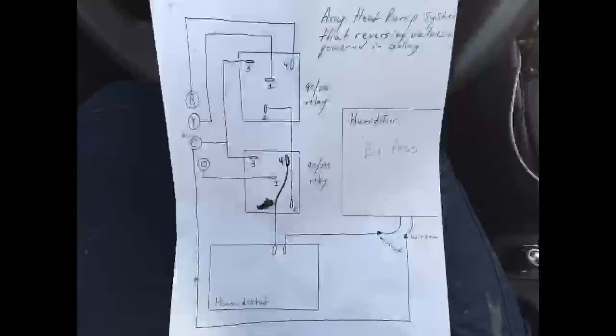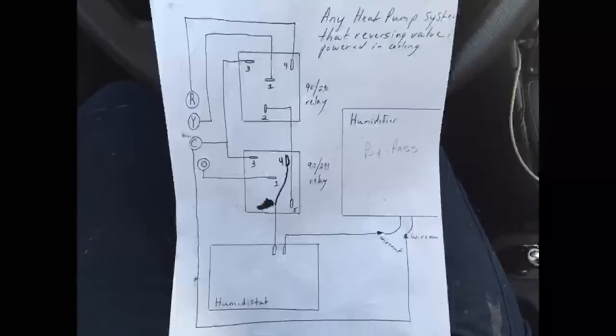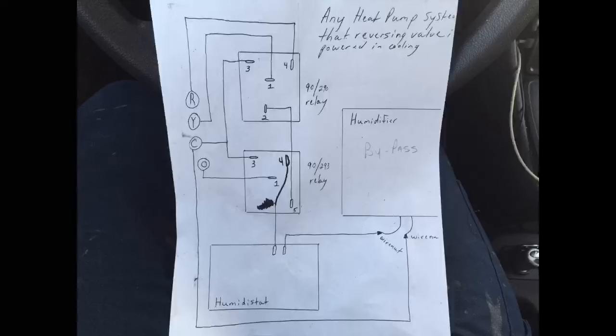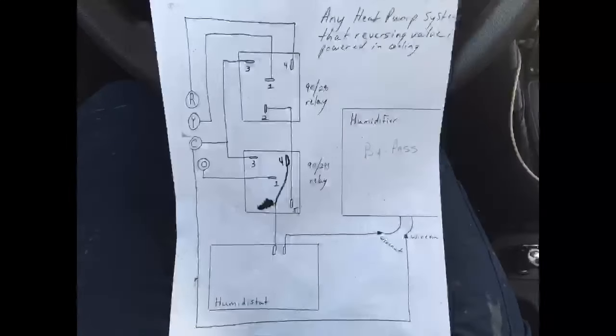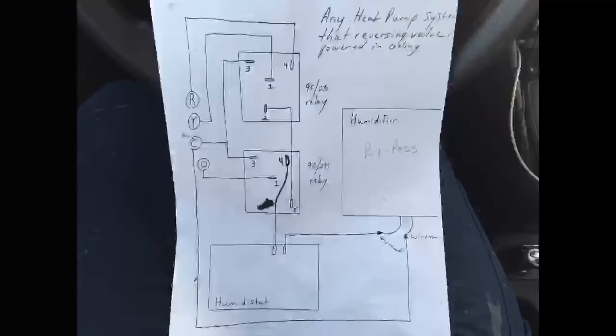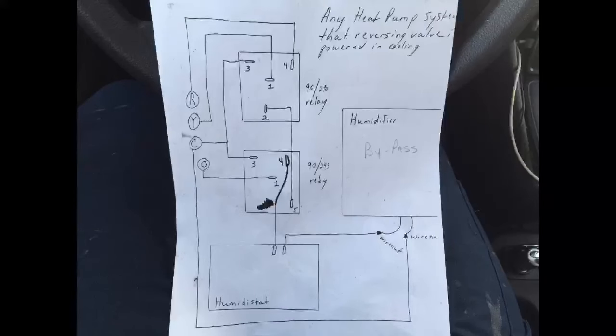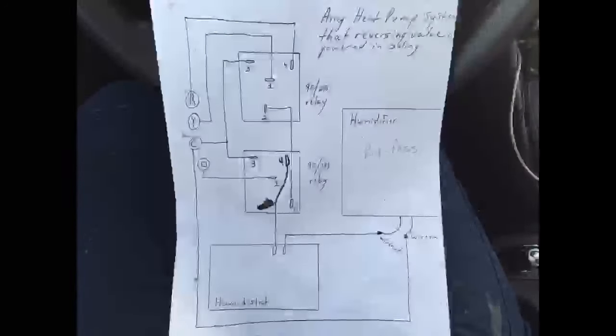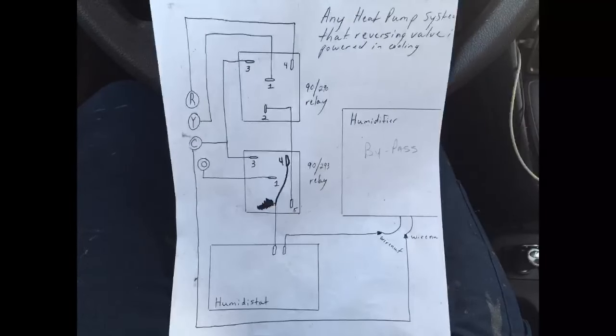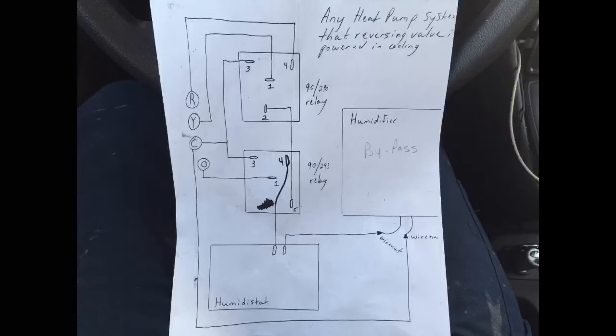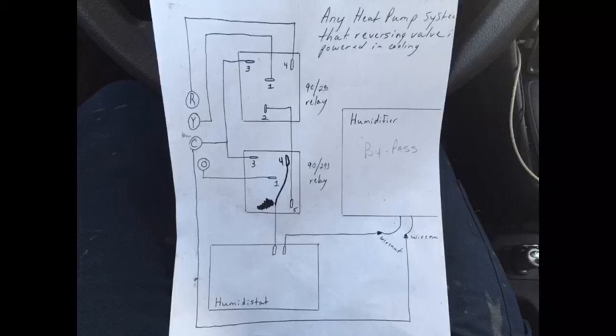Notes on the upper right show this is a relay setup for any heat pump system that energizes the reversing valve in cooling, and a standard bypass humidifier. With this particular layout, what we're trying to do is enable a humidifier to operate during heating but not during cooling. So you've got your common circulating through to all of your common sides of your 24 volt coils, and you've got power from the O terminal and power from the Y terminal, and then in this particular diagram the power going to the humidifier is delivered by the R terminal.